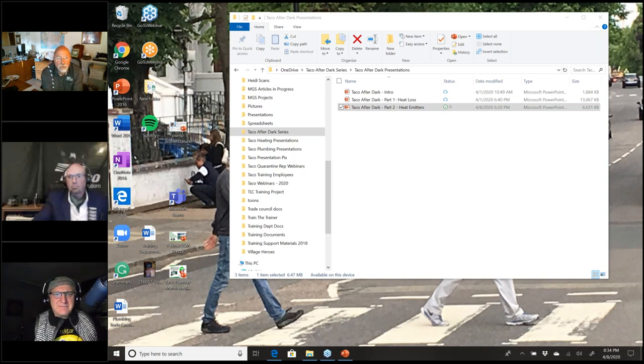So I guess you can flow too much fluid in a system, and the main worry at that point in time is high velocities, velocity erosion, corrosion, banging zone valves. A problematic noise, you know, things like that. One of the arguments a long time ago was saying, well, if I run the water too fast, it won't give time for the BTUs to jump off the train. Well, that was a nice story when they were telling it.